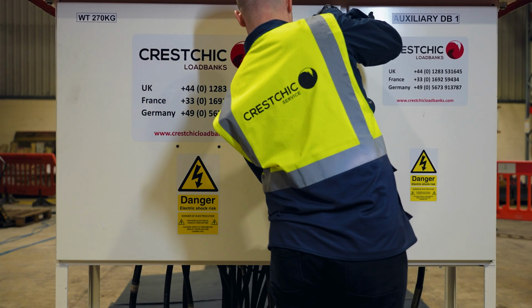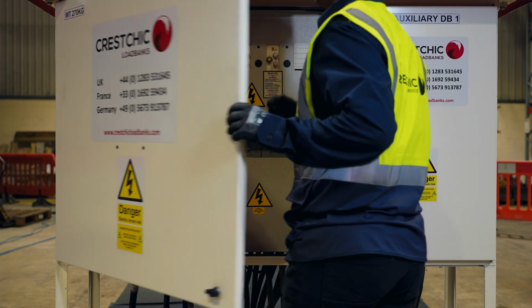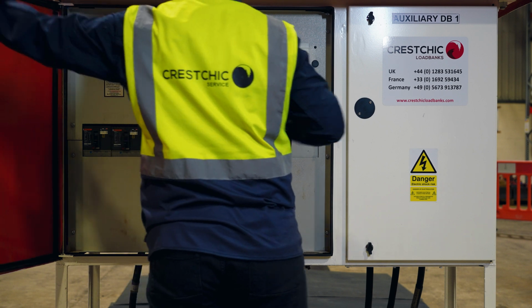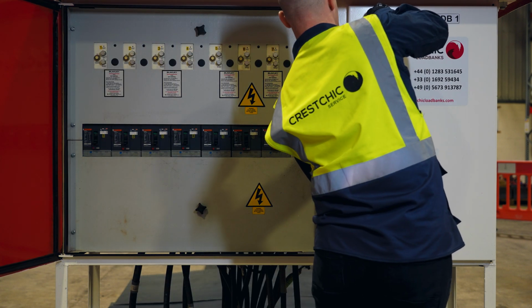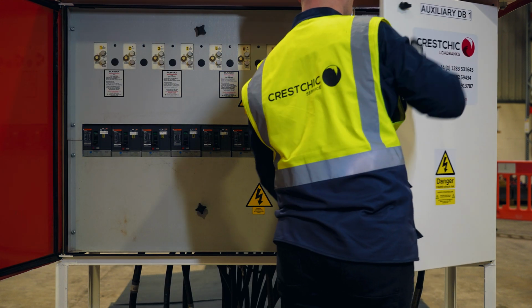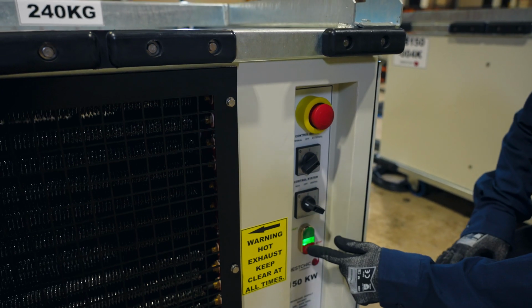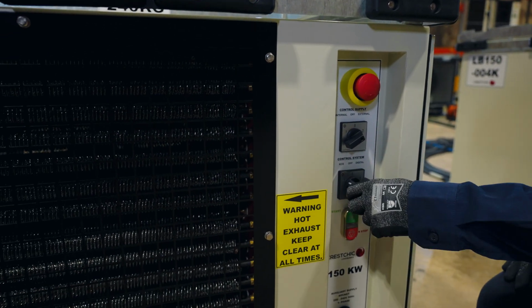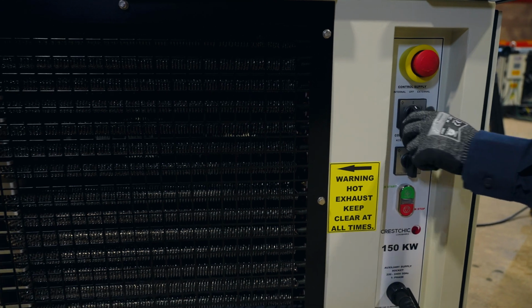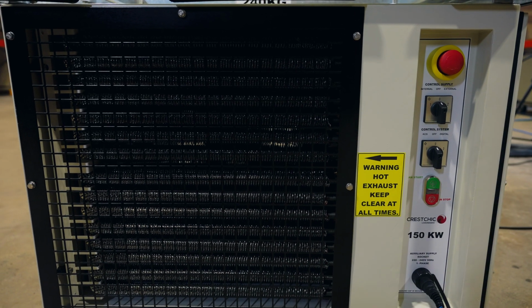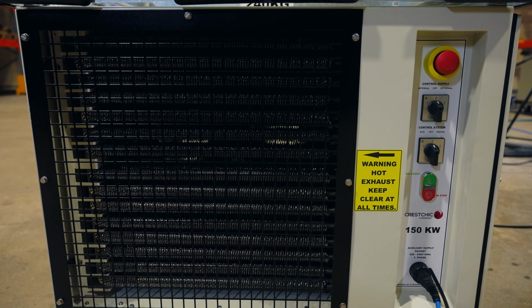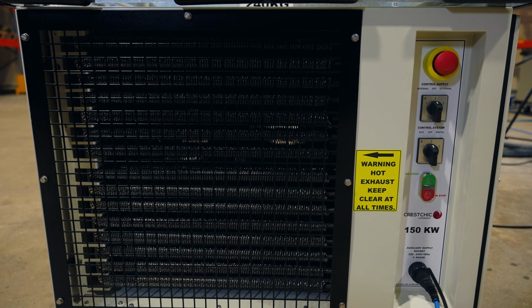Once the load testing has been completed, providing an auxiliary supply is being used to power the load bank's control circuit, the load supply can be turned off to the load banks. The load banks require a 4-minute cool down with no load present. Therefore, after 4 minutes have passed, the stop button can be pressed to switch the load banks off, and the control supply switch can be switched to the off position.